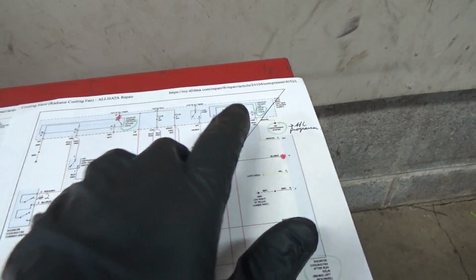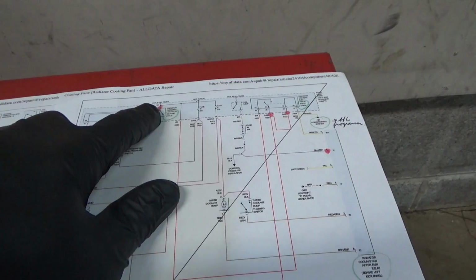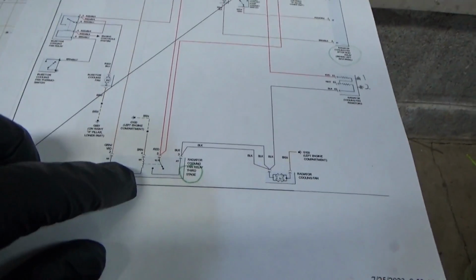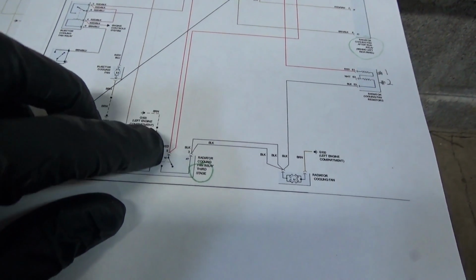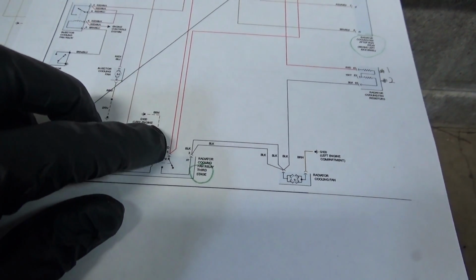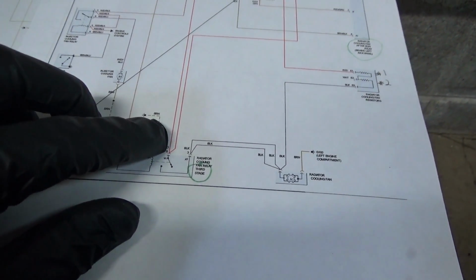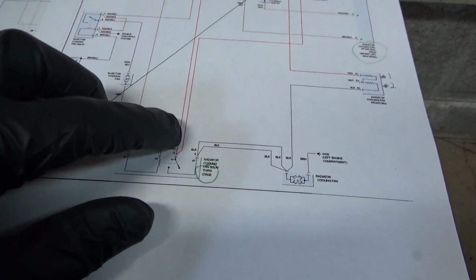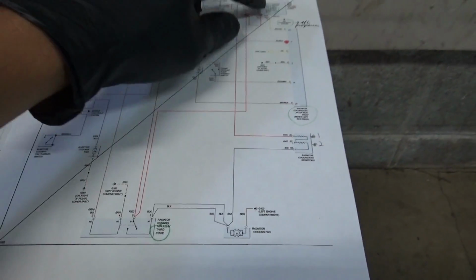So stage 1, stage 2, and stage 3 should all be hot on terminal 30. That's on the load side. So what we could easily do is remove the relays and just jump 30 to 87 on each one of these relays and see if the fan is capable of spinning on low, medium, and high speeds. That'll at least rule out the load circuit, and then we can focus on the control side and the relays themselves.